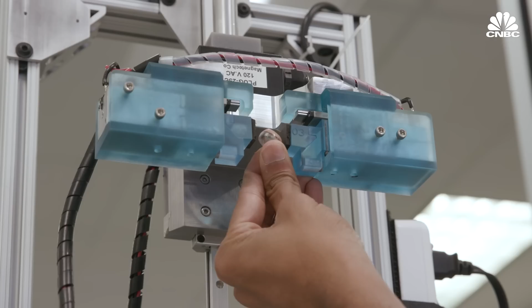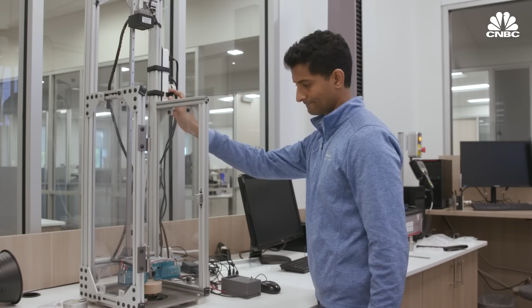Engineers also inspect to see if they can withstand extreme conditions like dust buildup as well as impact against a hard surface. A drop test, which in a calibrated fashion can suspend the device and slam it down into the floor at a far greater force than would likely happen when a hearing aid user was actually wearing their devices. In what company officials refer to as its CSI lab, hearing aids are also tested for moisture resistance by being submerged in a meter-deep column of water for half an hour.